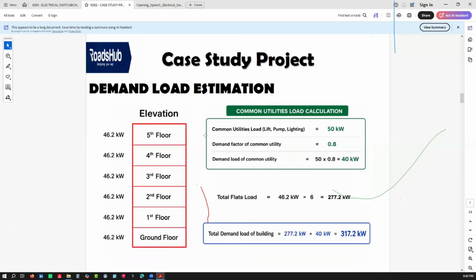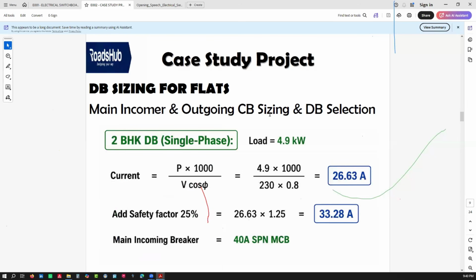When you're calculating your distribution board, you need to get the total amount of power for that specific board, and it's for demand load. Then you need to calculate your current, because we need to start with the main incomer and then size the outgoings, because outgoings can be supplying the different loads we've talked about. So you get this formula. For single phase, to come up with a current value, you have two methods. For people who study with us, we use normal conversion tables online. But there's a simple formula: power in kilowatts divided by rated voltage times power factor. So design power factor estimations are already there.